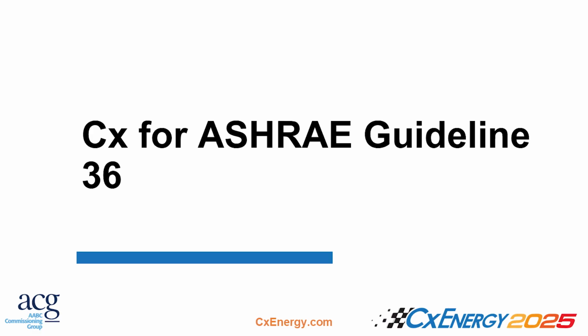We hear a lot from folks around ASHRAE Guideline 36. It's too complicated. Does it even work? My building operator doesn't know how to use it, so he disables it. He goes in and just overrides the set point to 55 Fahrenheit, or all kinds of stories. That's the building operator. We also hear that commissioning agents don't know how it works either, right?